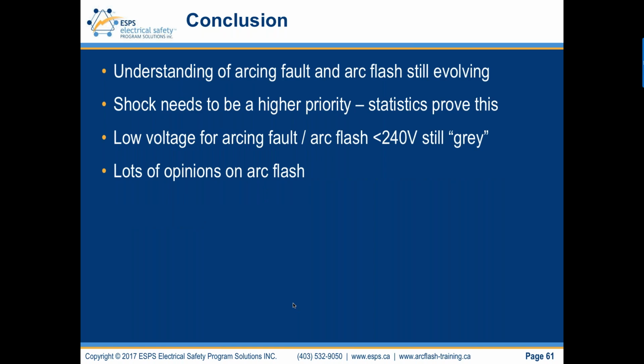So our understanding of arcing fault and arc flash is still evolving. Shock needs to be a higher priority. Statistics prove this. Low voltage for arcing fault and arc flash, less than 240 volts, is still a gray area. Lots of opinions on arc flash. Conservative or maybe too high risk. I believe the opinions that ESPS has and that I have personally are reasonable and practical interpretations of arc flash and shock hazards and how to interpret NFPA 70 and Z462.